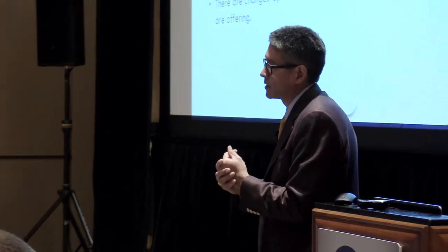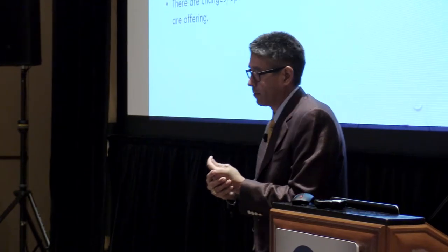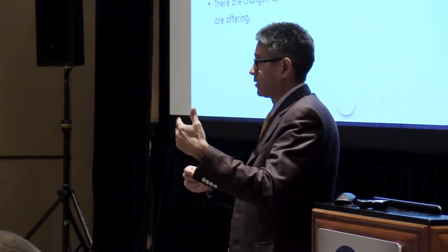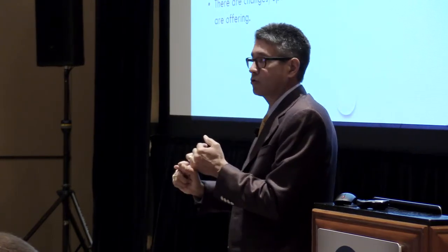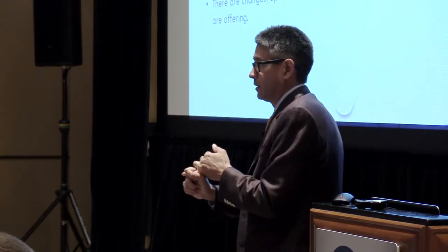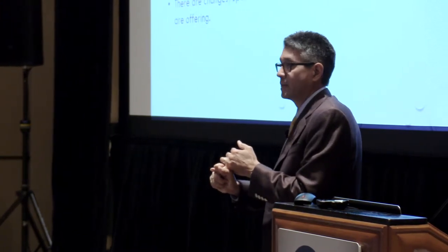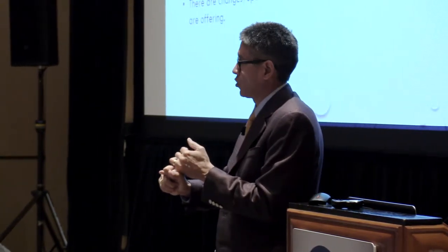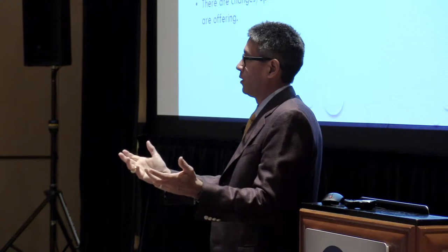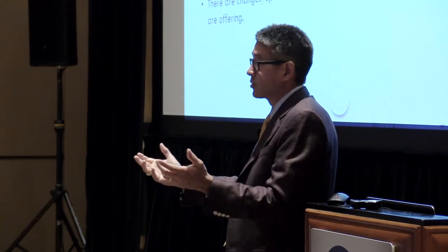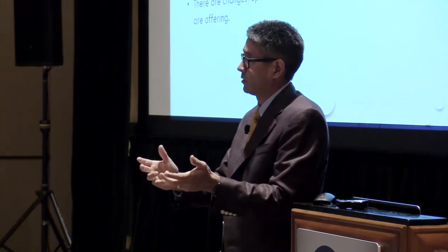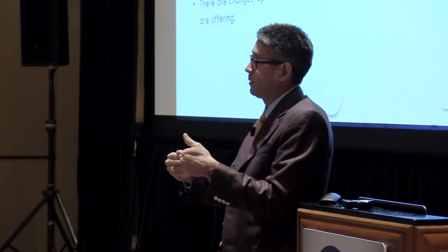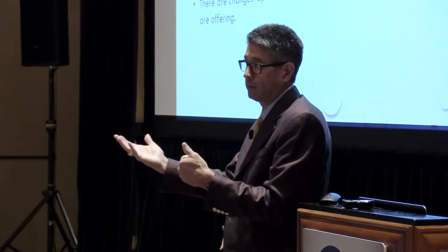Now that said, probably in the last 6 months, you've probably seen some of the different manufacturers out there publicizing all the different ways now that they're starting to do it. You're starting to see them tag an ultrasonic flow meter on the inlet of that control valve to give you water flow, to now start controlling to a water flow amount. Okay, so now you're going to sit there and say, if that's what we're going to do, your control strategies are probably going to change a little different, and now you can start thinking of it maybe more as a pressure-independent system like you do a VAV system.